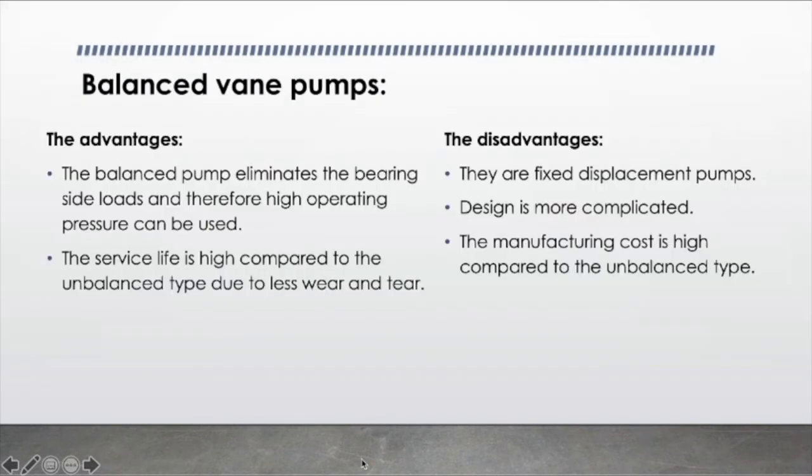Balanced vane pumps eliminate the bearing side loads and therefore high operating pressures can be used, and the service life is high compared to the unbalanced type due to less wear and tear. The disadvantages: they are fixed displacement pumps, design is more complicated, and manufacturing cost is high compared to the unbalanced type.